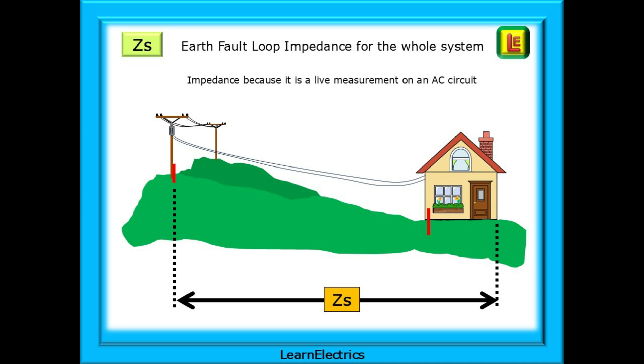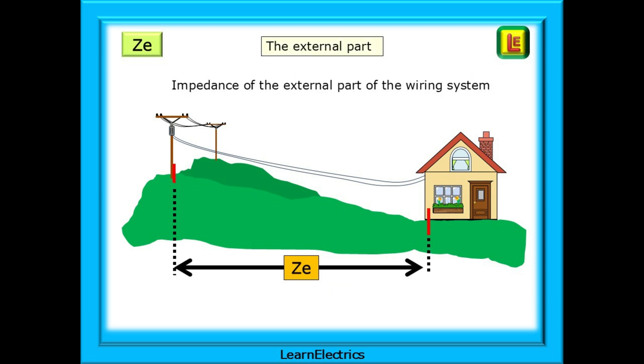We call it an impedance because it is a live measurement on an AC circuit, but it is still measured in ohms. ZE is the impedance of the external part of the wiring system. In a dwelling, this will be from the consumer unit, out of the property, into the general mass of earth, and back along the line conductor to the consumer unit.